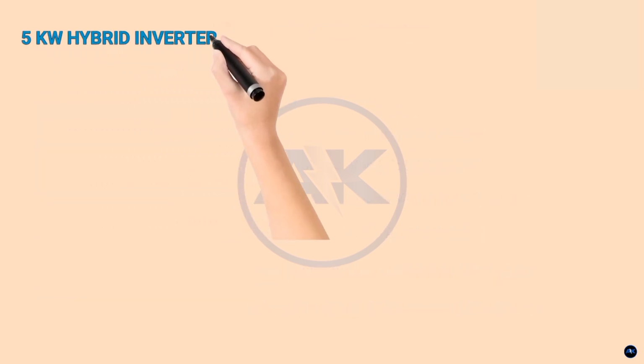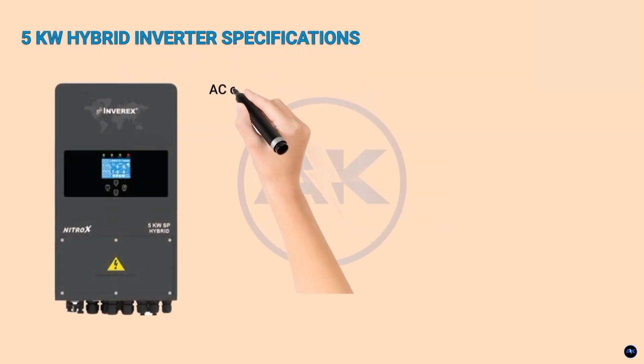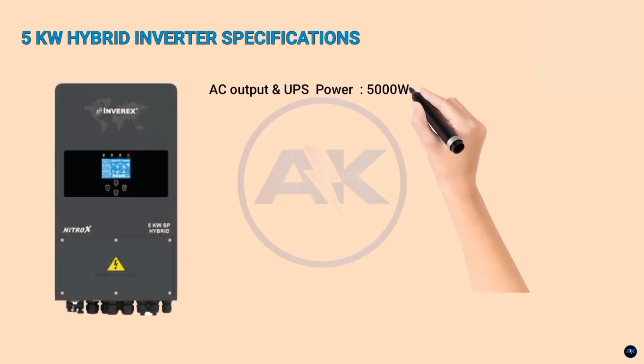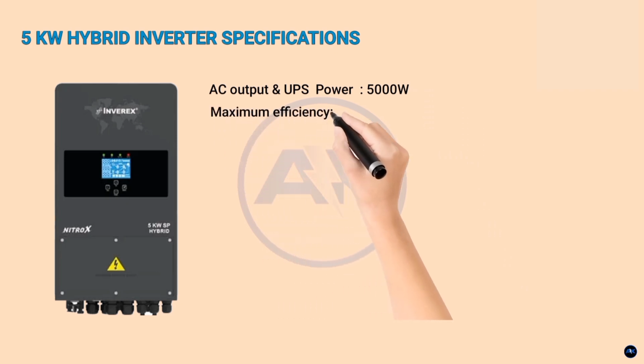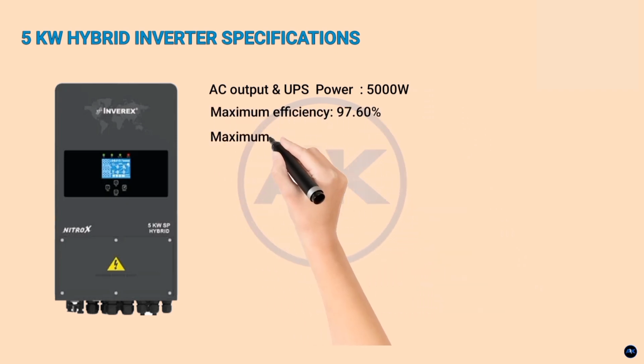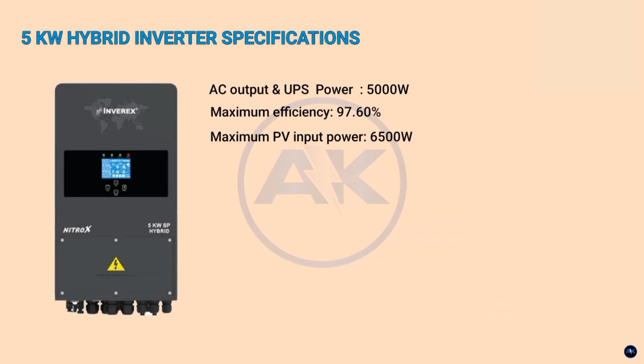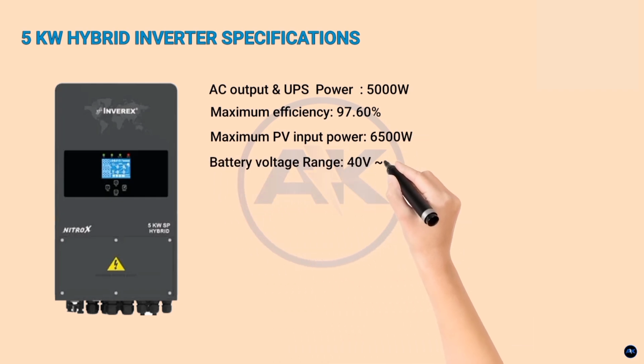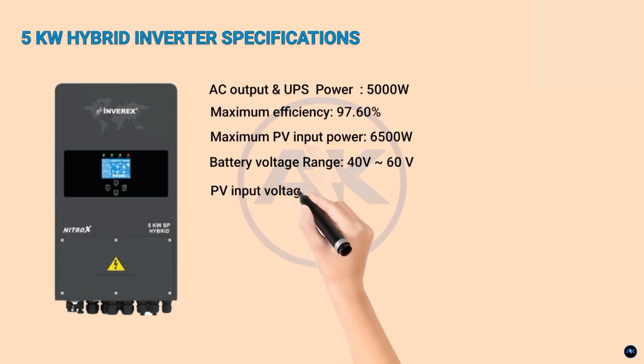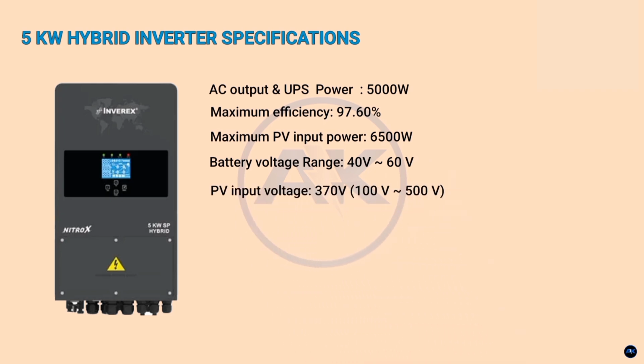For the 5 kilowatt hybrid inverter, we have the AC output and UPS power of 5000 watts or 5 kilowatts. Maximum efficiency is 97.6%, maximum PV input power is 6.5 kilowatts or 6500 watts. Battery voltage range is 40 volts to 60 volts. The recommended DC PV input voltage by the manufacturer is 370. That's the ideal VOC voltage. The minimum is 100. The maximum is 500 volts.